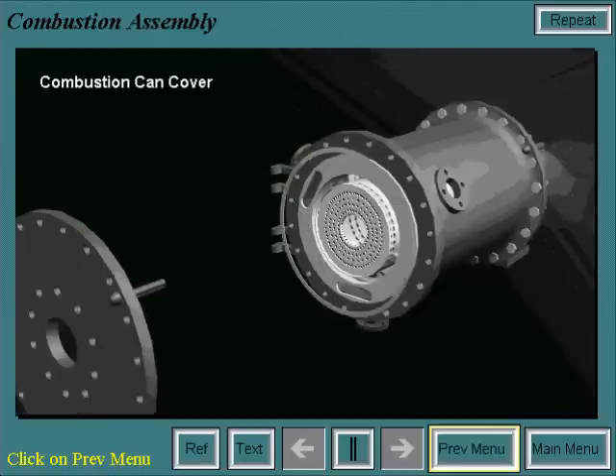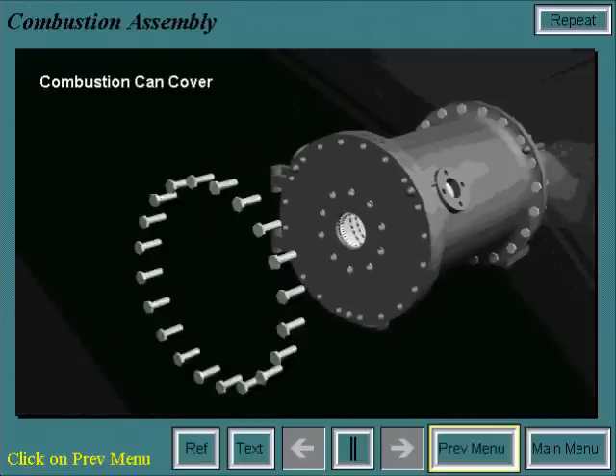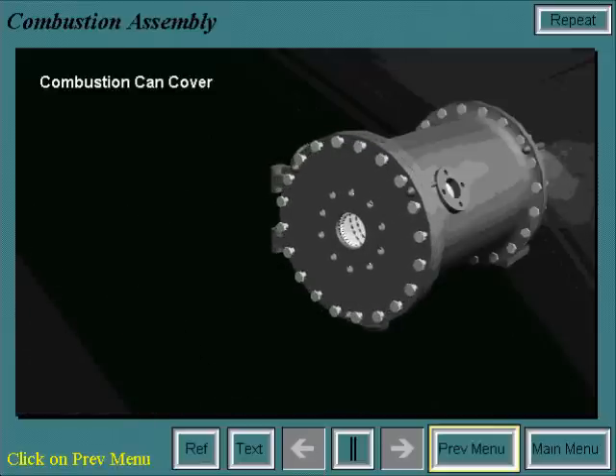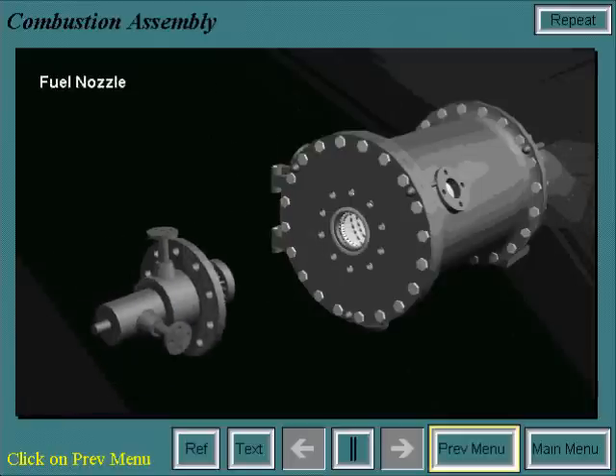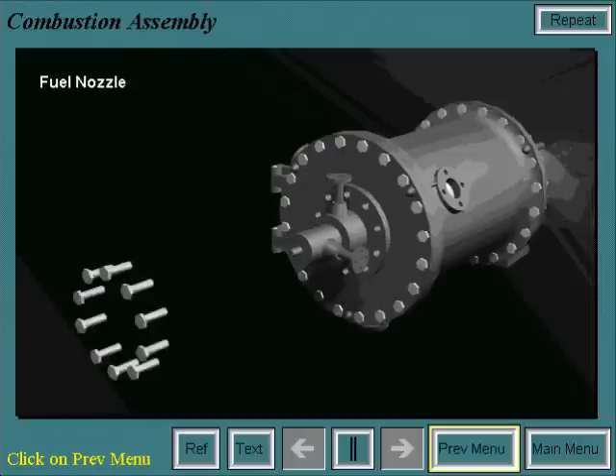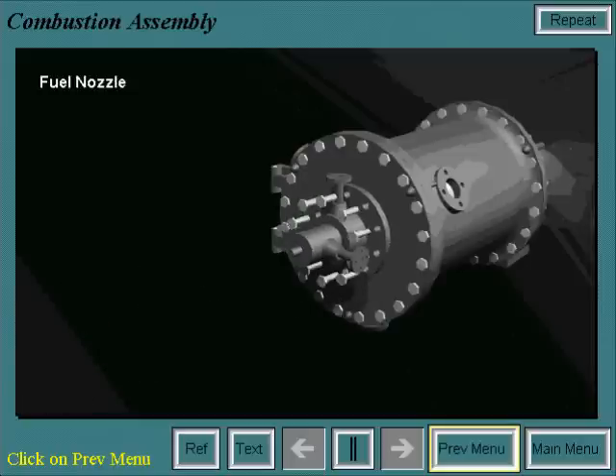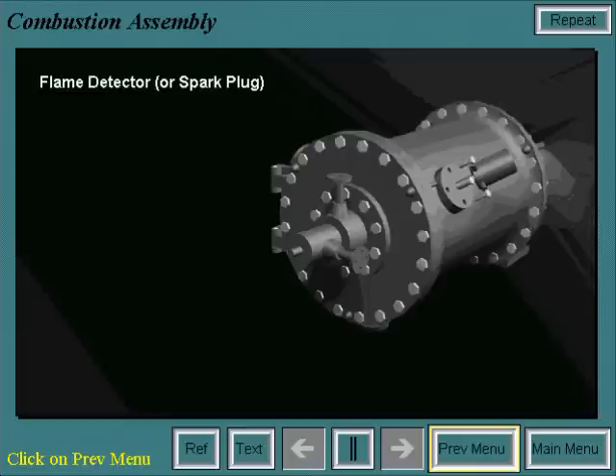Retaining clips keep the crossfire tubes in place. Next, the combustion can cover is bolted onto the combustion casing, and then the fuel nozzle is installed onto the combustion can cover. Spark plugs and flame detectors are also installed on certain combustion cans depending on the vintage of the unit.